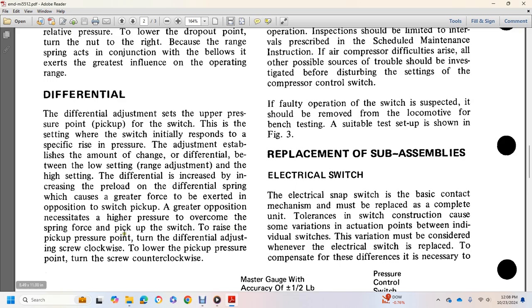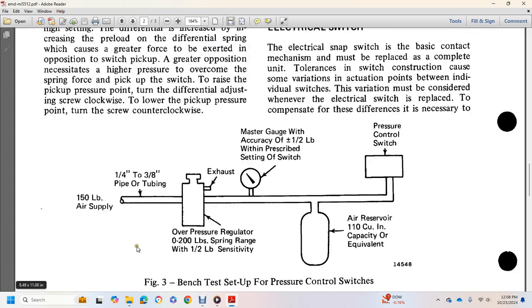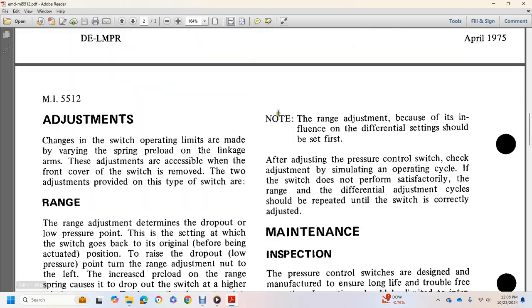To change the pickup pressure point, turn the differential adjustment screw clockwise to raise the pickup pressure point, and counterclockwise to lower it. Note: the range adjustment will influence the differential setting, so the range should be set first. Adjusting pressure control switch.